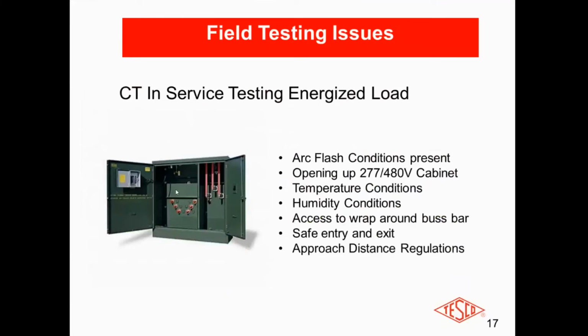So for CT in-service testing with an energized load, we have flash conditions present. We're opening up a 277-480 cabinet. We have temperature conditions too - I live in Arizona, and I can tell you, having done this myself with a few local utilities, it's really not fun to stand next to a cabinet that's obviously really hot. That whole metal cabinet can get heated up to over 180 degrees. It gets very, very hot, and you're wearing your full suit and everything, so you've got to be real careful.